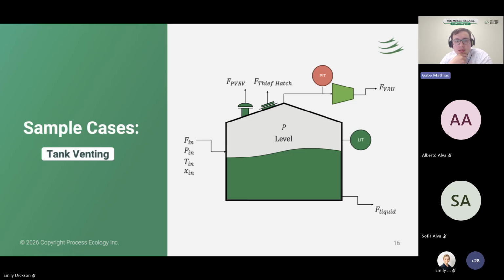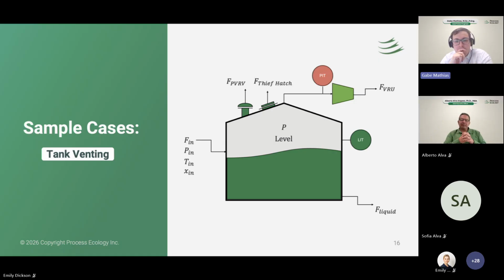Those are there just to protect the tank from explosion or implosion, depending on the scenario. If the pressure reaches a certain point, then the safety device opens and relieves to atmosphere so that the tank integrity isn't compromised. And what we're trying to find is the flow rate of vapor leaving the tank, and specifically the flow rate leaving through the safety devices versus leaving through the VRU.